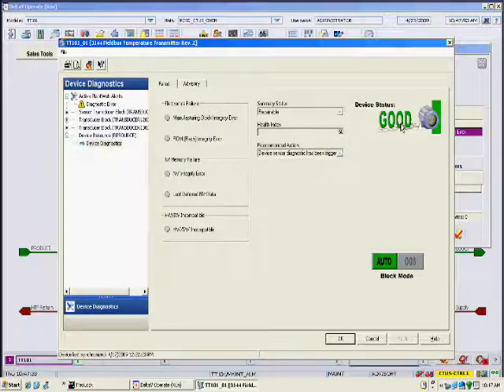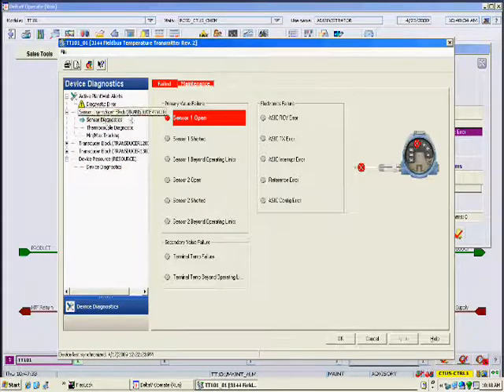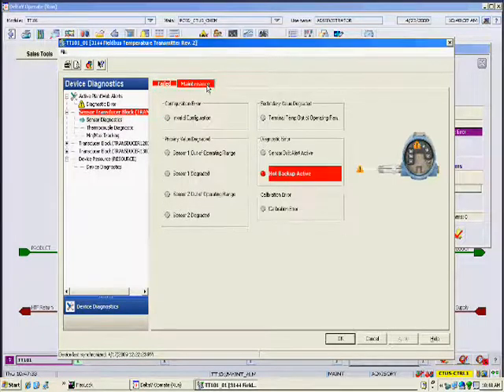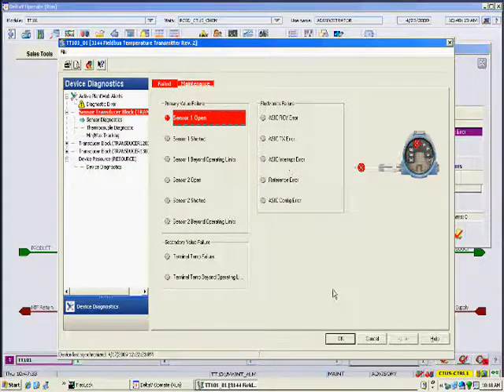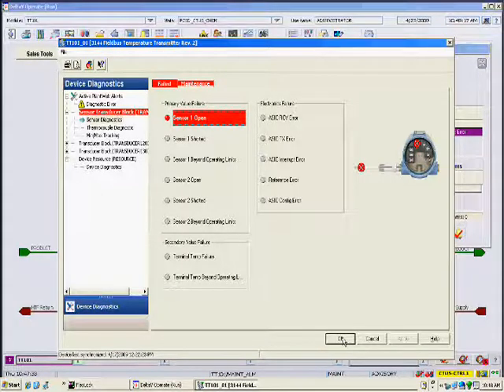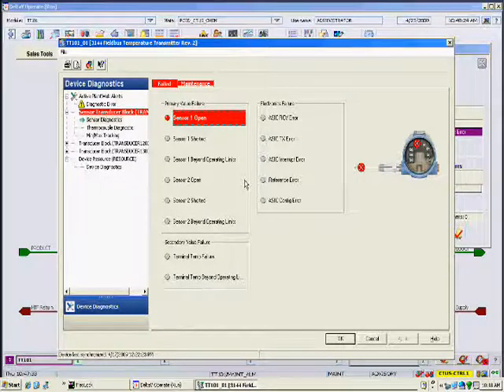Control continues as usual. The operator follows the red tabs to see the detail of the error. The detailed diagnostics reveals first that sensor number one is broken, but also that the transmitter's hot backup function is activated — that is, the transmitter has switched to a second redundant sensor and is therefore still able to measure, enabling control to continue. Conditional images illustrate that the problem is related to the sensor or the wiring. The operator cannot fix the problem but can call on a maintenance technician to do the repair.